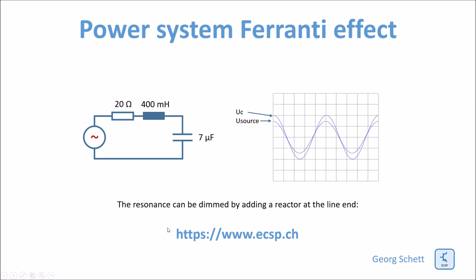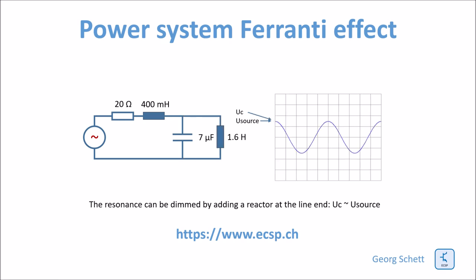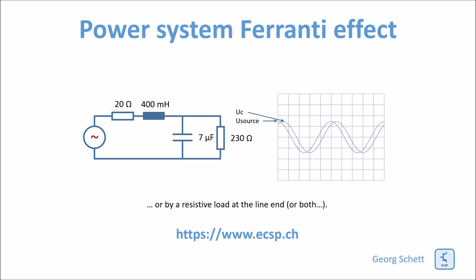This voltage increase can be mitigated by adding a reactor at the line end. Here there is a reactor and you can see that the voltage at the end of the line is comparable or even equal to the source voltage. The voltage increase is also mitigated if you have a heavy load at the end of the line — in this case a 230 ohm resistance. The output voltage is no longer higher than the source voltage, and you can also observe a phase shift between the source and the line end voltage.